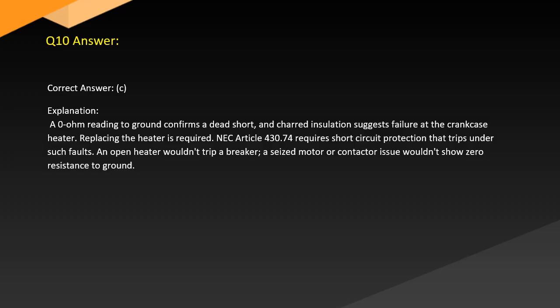Answer. Correct answer: C. Explanation: A 0-ohm reading to ground confirms a dead short, and charred insulation suggests failure at the crankcase heater. Replacing the heater is required. NEC Article 430.74 requires short circuit protection that trips under such faults. An open heater wouldn't trip the breaker, and a seized motor or contactor issue wouldn't show zero resistance to ground.